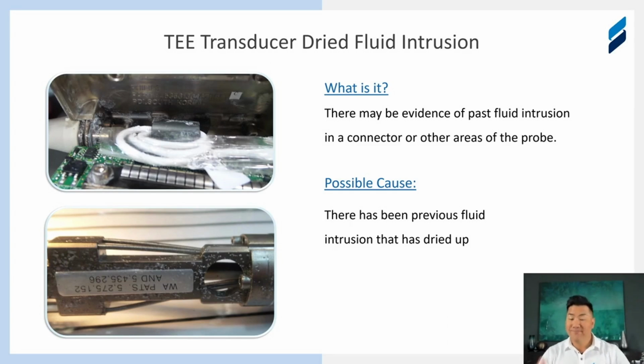And so this could be really good news and really bad news, typically not in between. The good news could possibly be that the probe works fine, just needs to be cleaned out, and you're off to the races. It's good to go, ready for scanning again. The other is, well, the fluid's been sitting on things for a very long time, and it has now corroded some metal electronics that just aren't salvageable anymore, which could result in a replacement. So these are things that we look for. I just want to show you that if it's not caught early, there is a higher risk of a probe being unrepairable because of the corrosion properties and the material deteriorating so much that there's nothing to work with anymore during a repair.